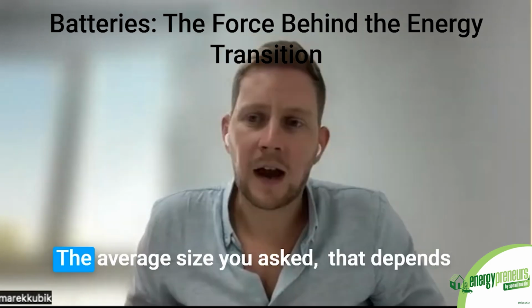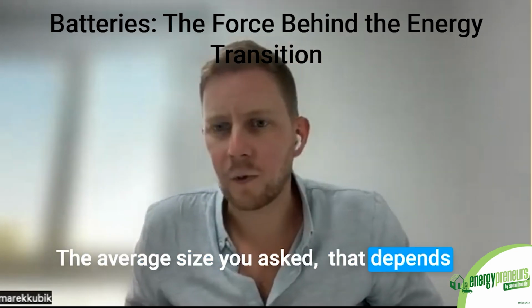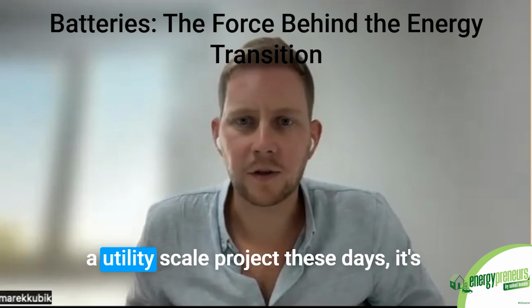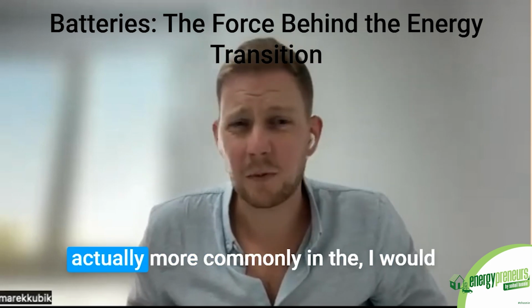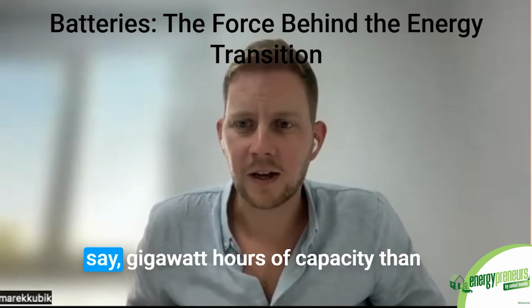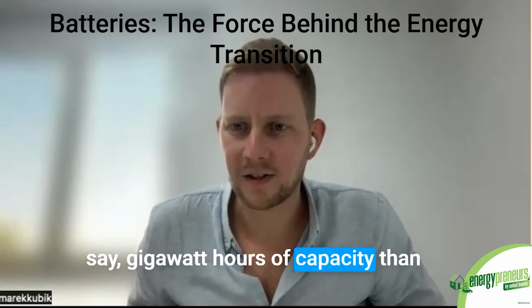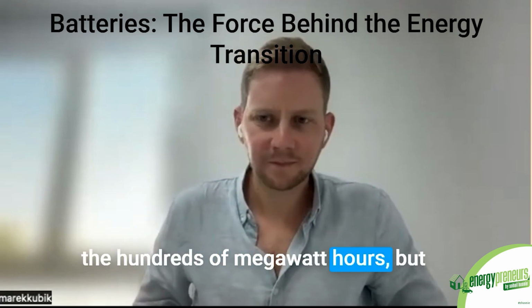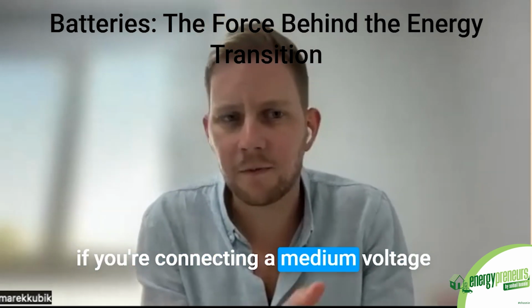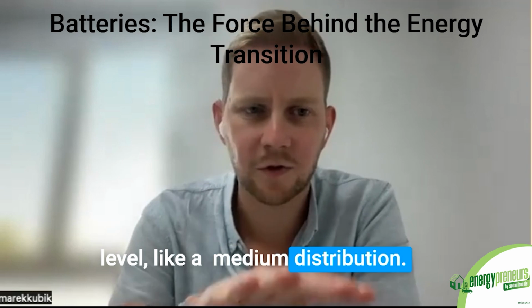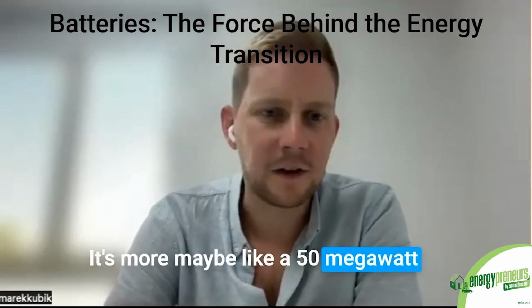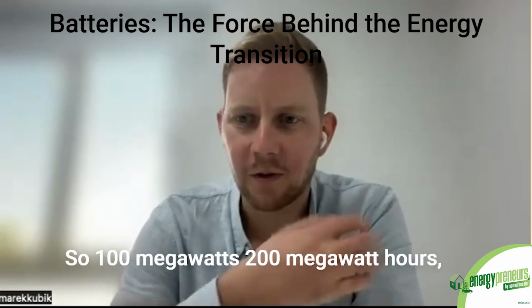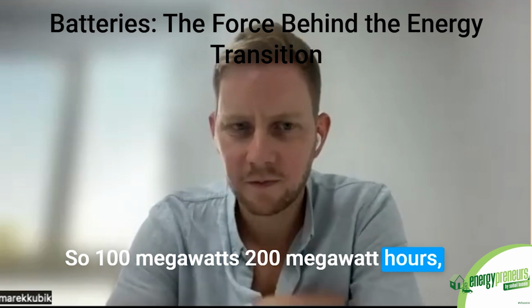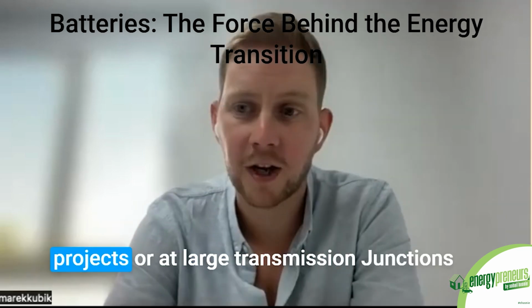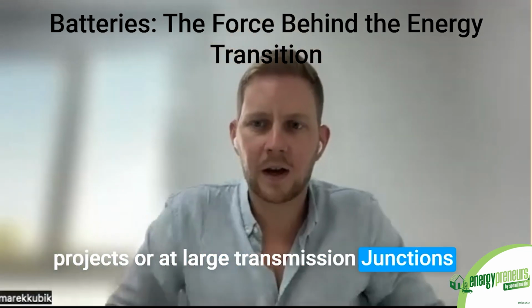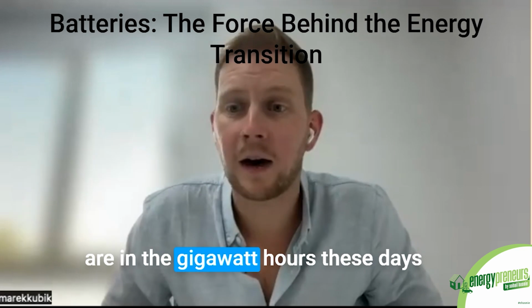And the average size you asked about depends where you're connecting to, right? For a utility scale project these days, it's actually more commonly in the gigawatt hours of capacity than the hundreds of megawatt hours. But if you're connecting at a medium voltage level, like medium distribution, it's more like a 50 megawatt system of 2 or 4 hours - so 100 megawatts, 200 megawatt hours. But the utility scale systems at renewable projects or large transmission junctions are in the gigawatt hours these days.